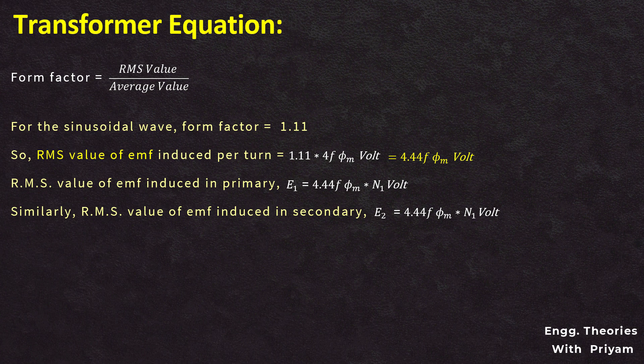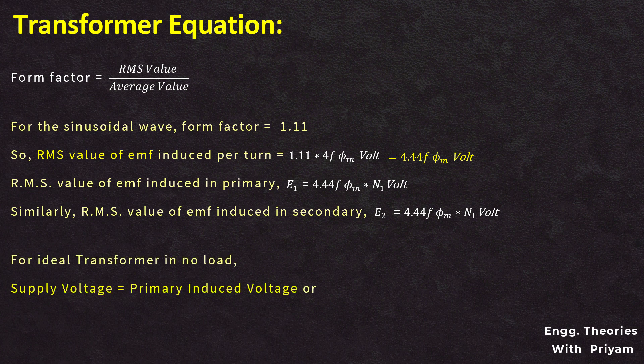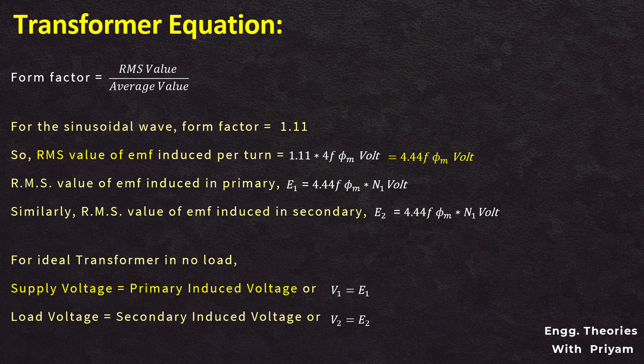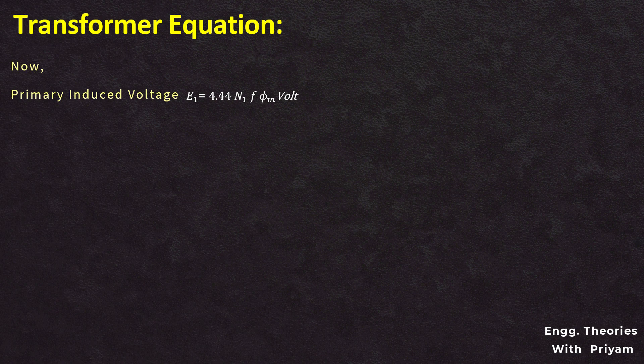For an ideal transformer at no load, the supply voltage equals the primary induced voltage, or V1 equals E1, and the load voltage or terminal voltage equals the secondary induced voltage, or V2 equals E2. So the primary induced voltage E1 equals 4.44N1Fφm volts, and the secondary induced voltage E2 equals 4.44N2Fφm volts.